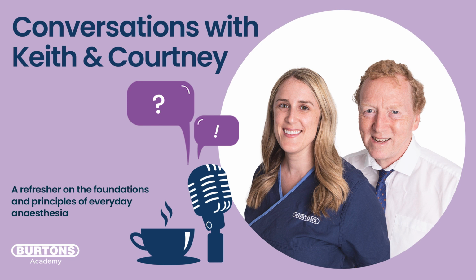And then we'll hopefully start to get some very accurate readings on our multi-parameter monitor and some waveforms for us to analyze. We should then start to see a waveform on the screen, and typically it looks mostly in character like a pulse ox waveform. So if you've not seen an IBP waveform before, it's going to have the same sort of outline as a pulse ox. But next to it, of course, we're going to get some systolic values, some diastolic values, and a mean arterial value. And this is the gold standard, so we can really start to believe those numbers.